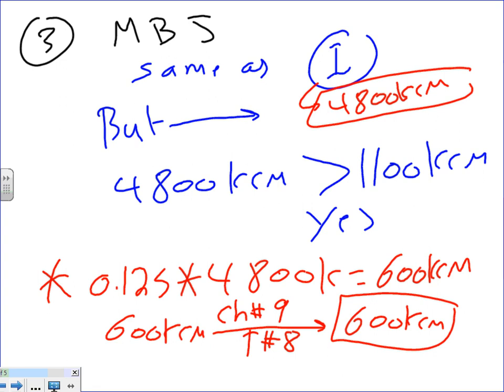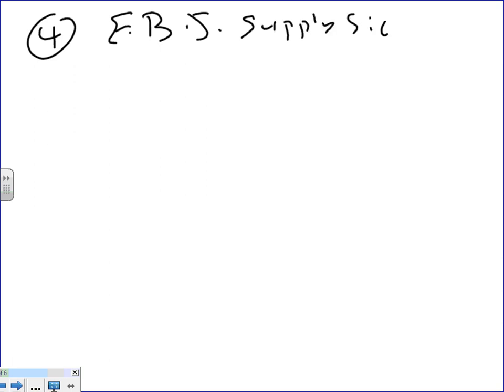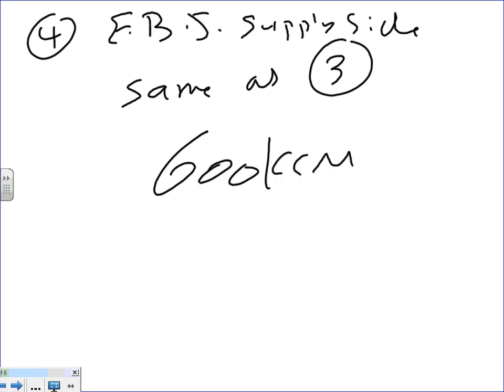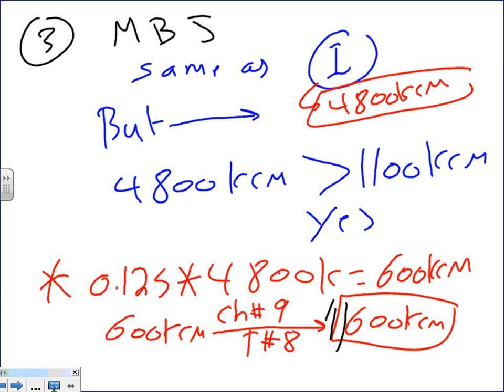What's number 4? Equipment bonding jumper on the supply side. Table 250. Can you guys see this is the same as number 3, right? So number 4, equipment bonding jumper, supply side. Equipment bonding same as number 3. So what would the answer be then? 600 kcm. How many? 1. Did I say how many of these here, guys? Always 1 here.